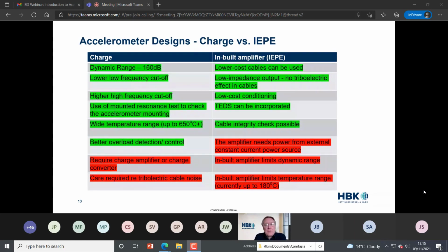Okay, so some of the relative benefits between charge output accelerometers producing picocoulombs and IEPE types, which are producing a voltage. Inevitably, when you introduce an amplifier into a very essentially simple system, you are going to impose constraints. The most important constraints that you impose by putting an amplifier in there is that you need external power to power the amplifier. The amplifier limits the dynamic range of the charge device, and it also limits the temperature range, currently to around about 180 C. Whereas with no amplifier inside the can, the range of a piezoelectric accelerometer is pretty huge.